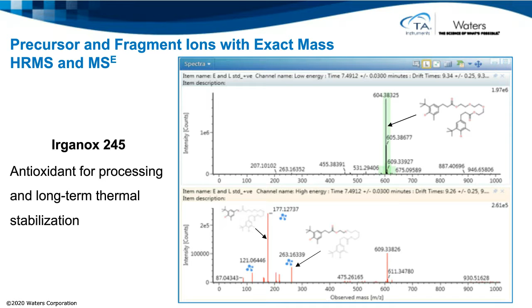When running our screening analysis, we want to find as much information as possible about the compounds in our sample. This helps to identify what the compounds are, be that through matching against the library or through structural elucidation. Here we can see the mass spectrum for Irganox 245, a common antioxidant. On the top, we can see the low energy spectrum containing the precursor ion. Below it is the high collision energy spectrum, containing the fragment ions associated with the precursor. Using high-resolution mass spectrometry, HRMS, and a capability called MS^E, in one analytical run we can simultaneously obtain both the accurate mass spectrum of the precursor and the fragment ions, providing us with information that we can use to both screen against the library and to help with elucidation of a structure.